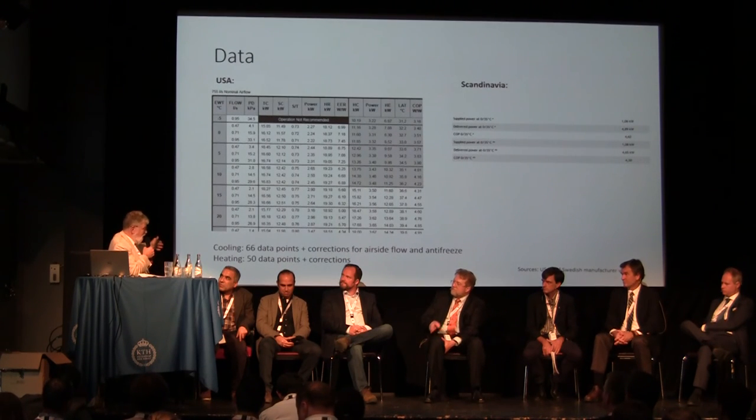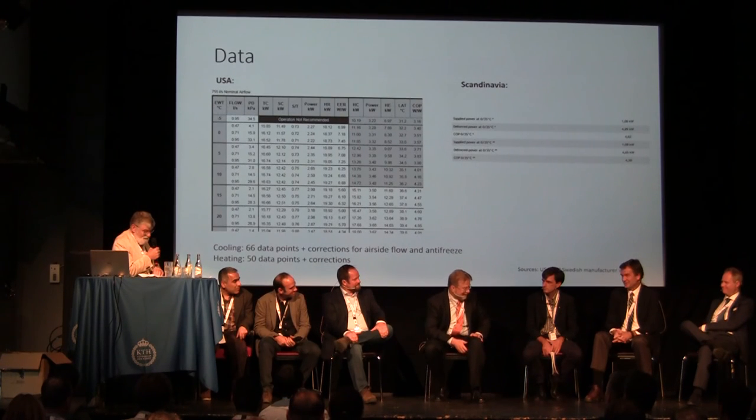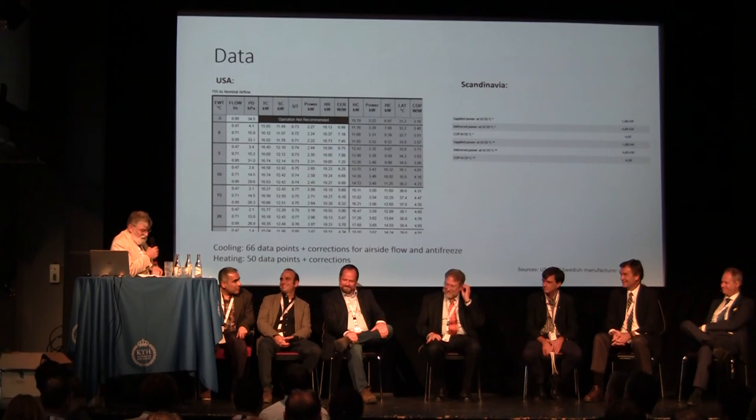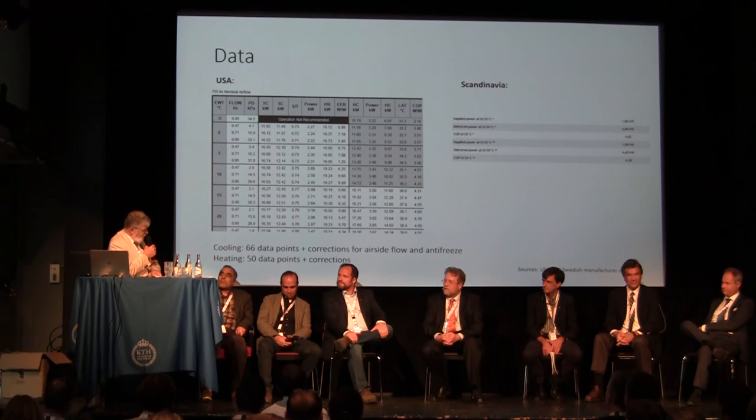I have actually been with a company that installed free cooling in a house outside Stockholm — reducing the incoming working fluid to 17 degrees, heated to 20, while rooms were kept at 22-24. But there were huge heat exchangers, and no condensation occurred because pipes were kept above the condensation temperature. Where we come from in the US, we would consider no condensation a failure because the house would be very humid if we didn't condense — we feel strongly we've got to get the water out of the air.